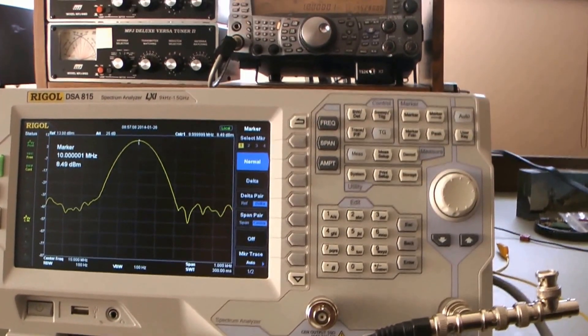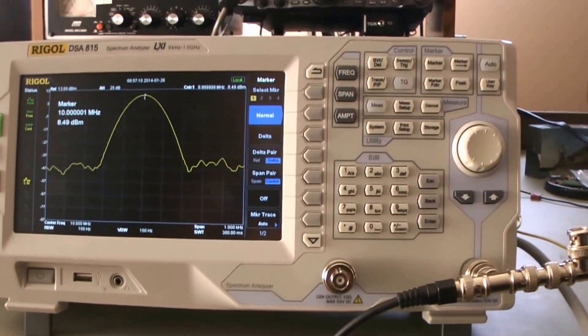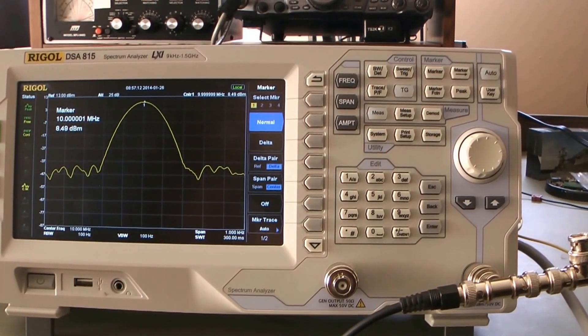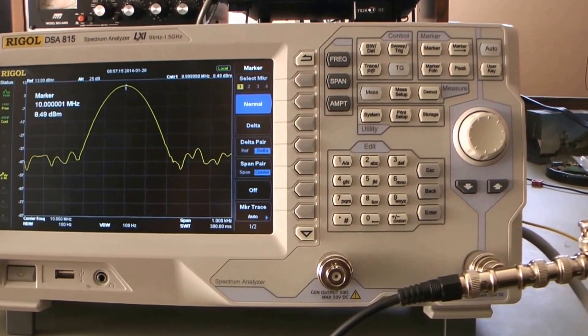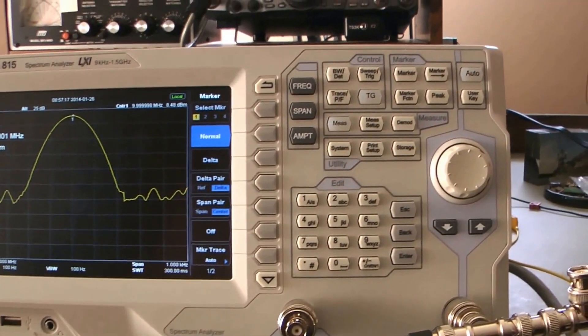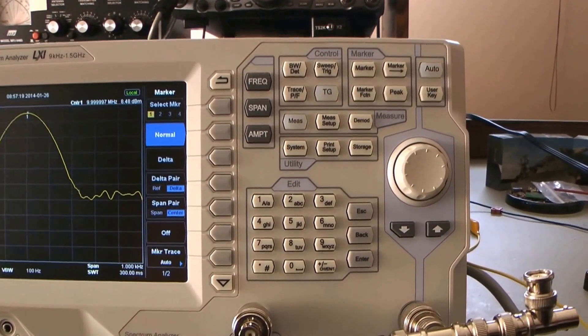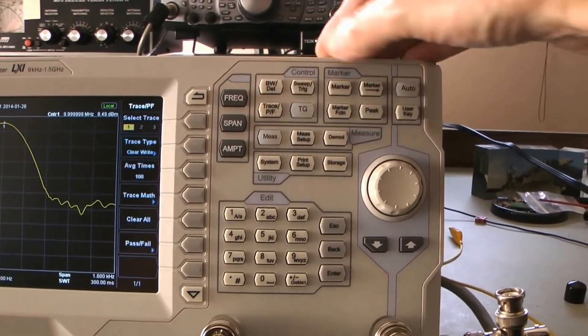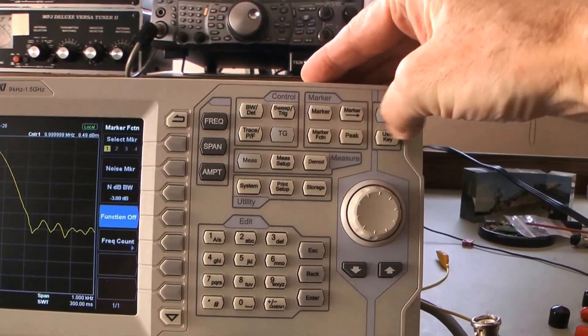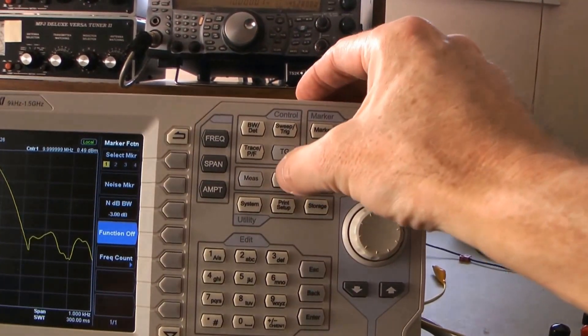Next thing to do is understand how you put it into calibration mode, and the Rigol documentation isn't very clear on that. So what you start off with is trace, tracking generator, function marker, measuring setup, system, print setup, storage.